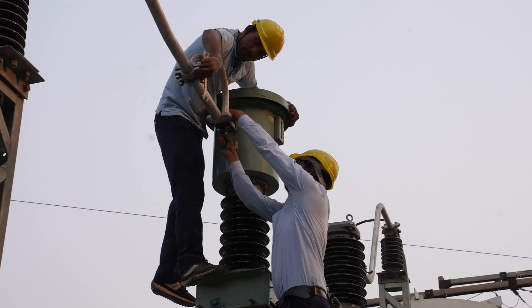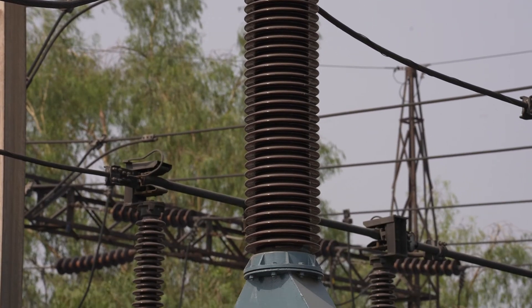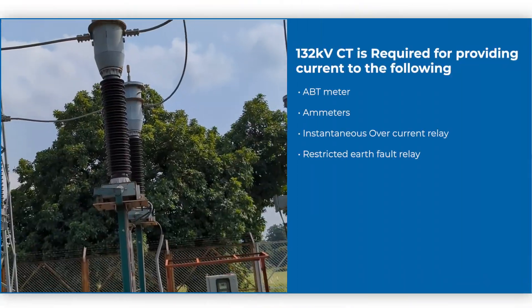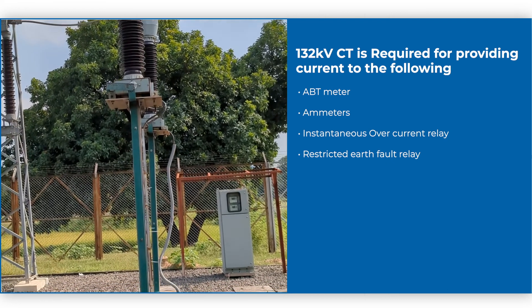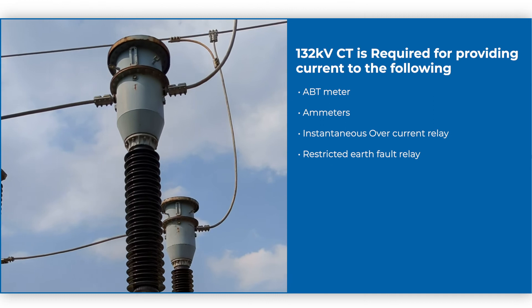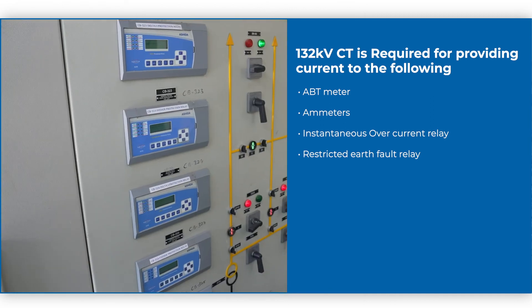This video is related to the maintenance and testing of current transformers provided in railway traction substations. The CT of 132 kV rating is provided in the ABT metering system as well as on the primary side of the traction transformer to sense or measure the current for the meters and protective devices.